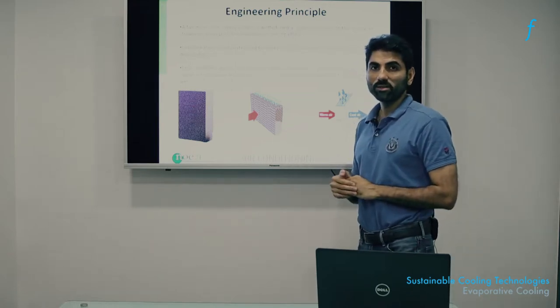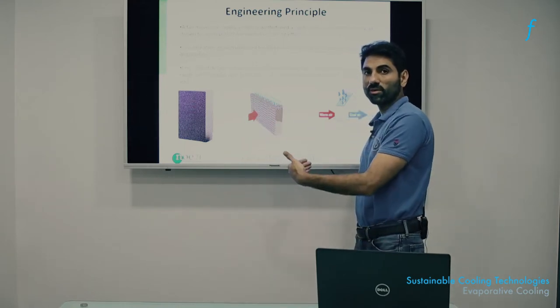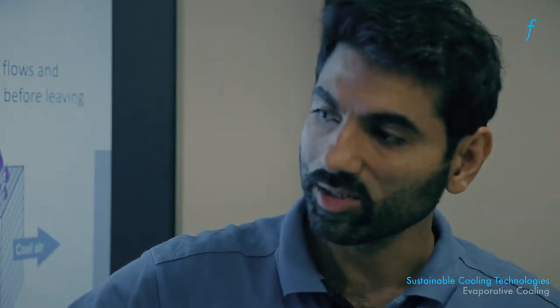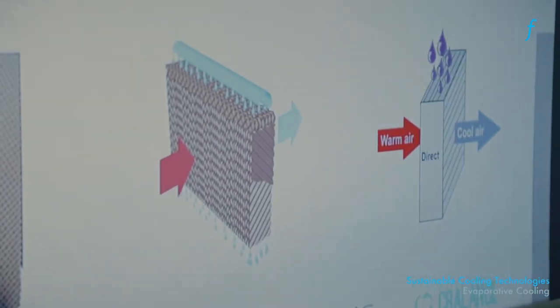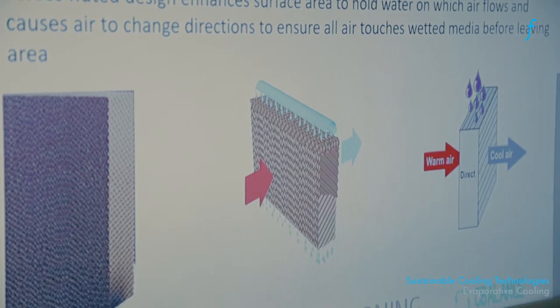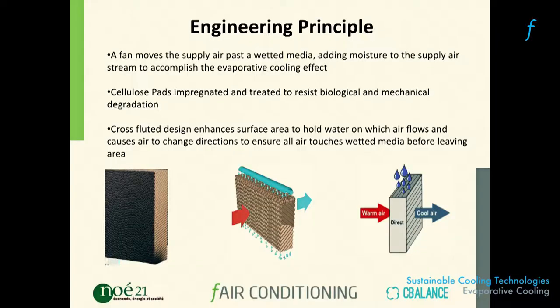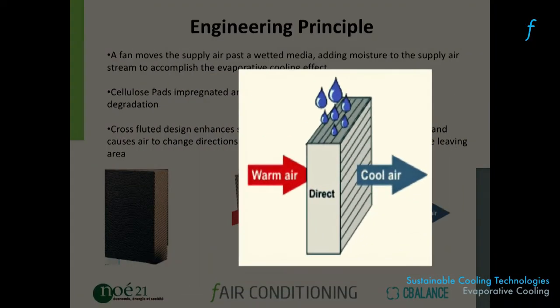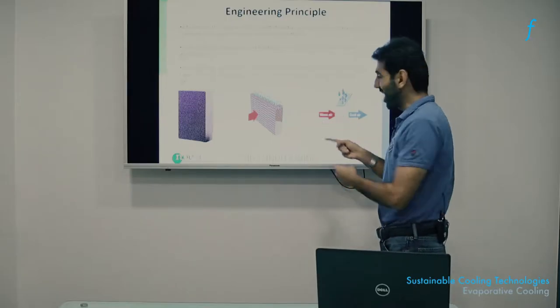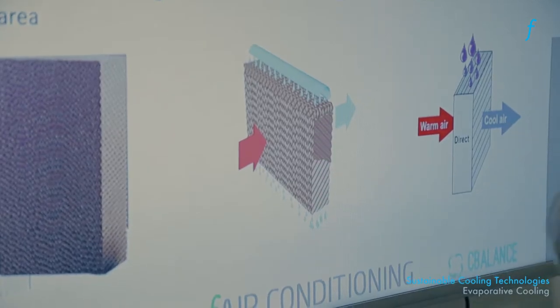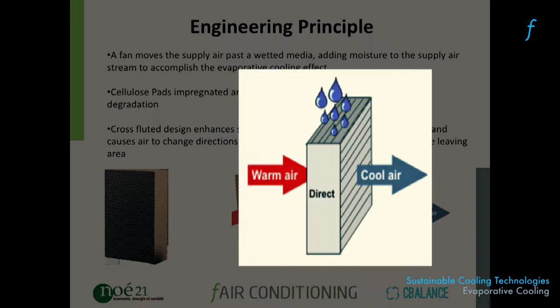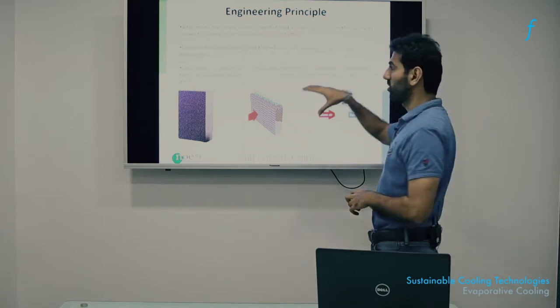A cellulose pad with a lot of surface area per unit volume is kept continuously wet. A fan blows warm air (around 42°C) through the pad. The water picks up the latent heat of evaporation from the air, and what comes out on the other side is cool but humid air, which cools people sufficiently in hot and dry regions of India. That's how a science principle is converted into an engineering technology.